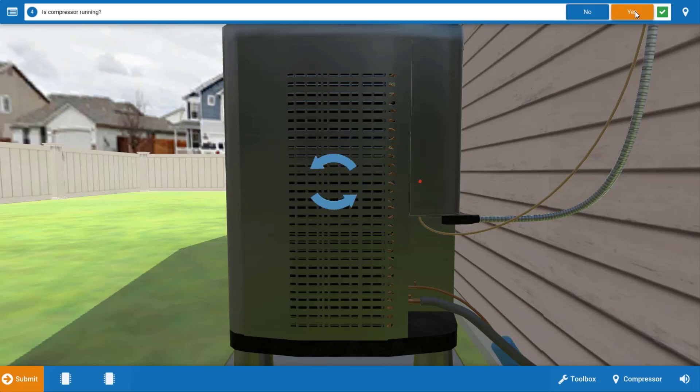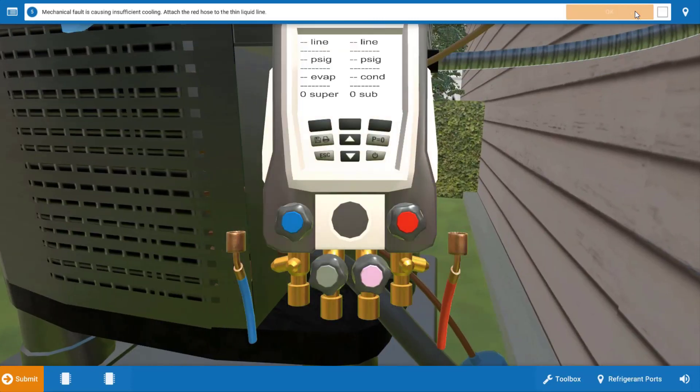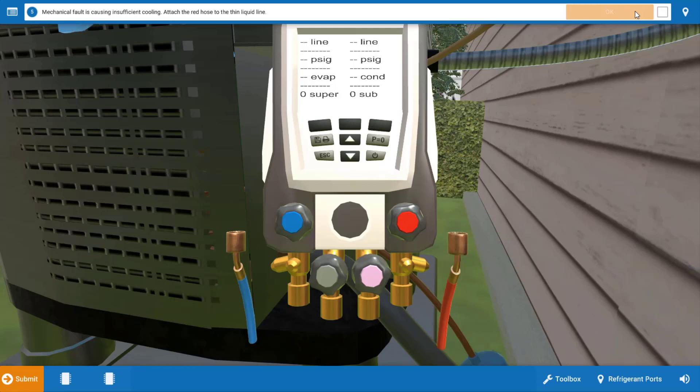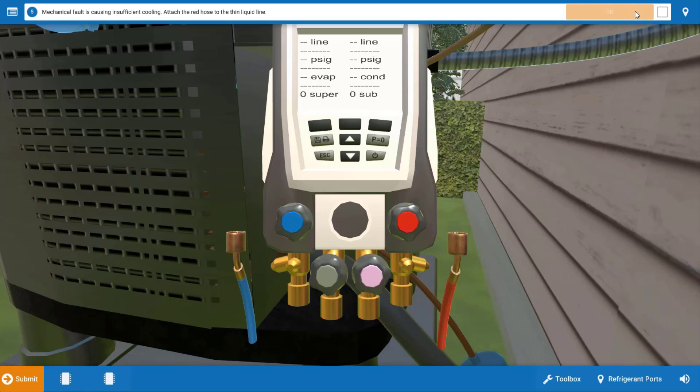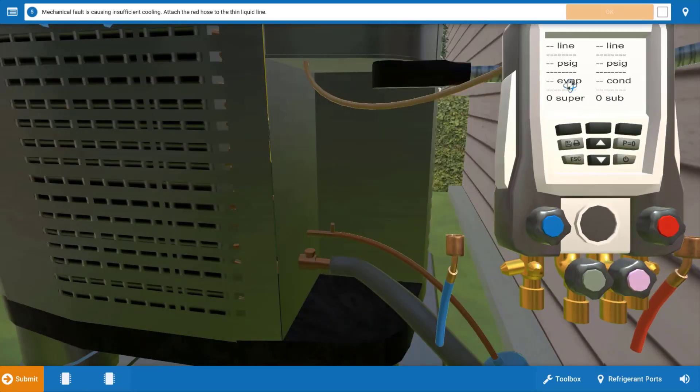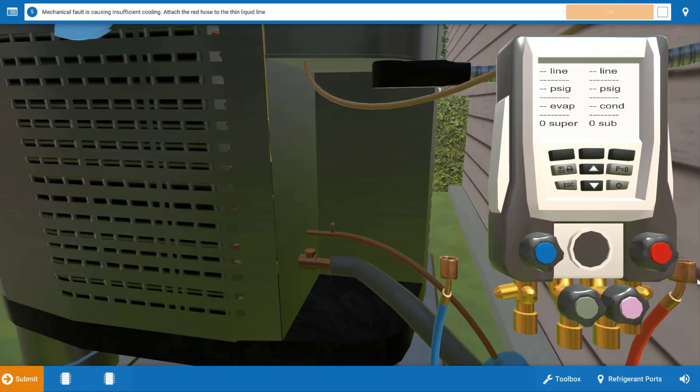This means we have a mechanical problem. All electrical loads are operational although I would tell you in some cases a severe overcharge of refrigerant or a severe undercharge due to a leak may cause the unit to cycle off on the high pressure or low pressure cutouts. But for this particular malfunction, it's not that severe and the units are continuing to run. Our next step once verifying it's not an electrical problem is to measure pressure as well as superheat and subcooling.